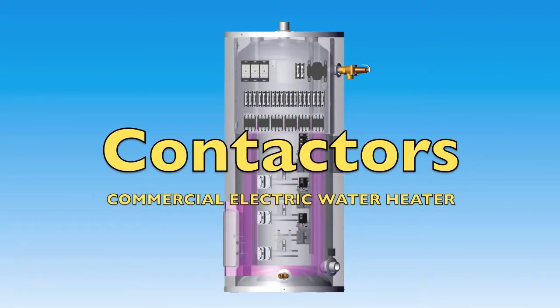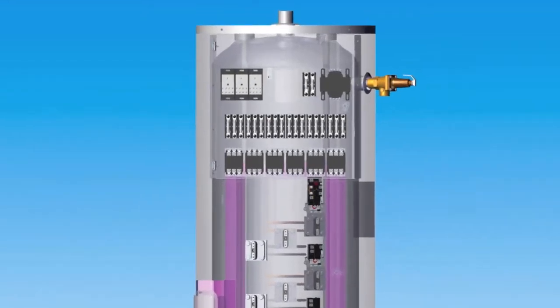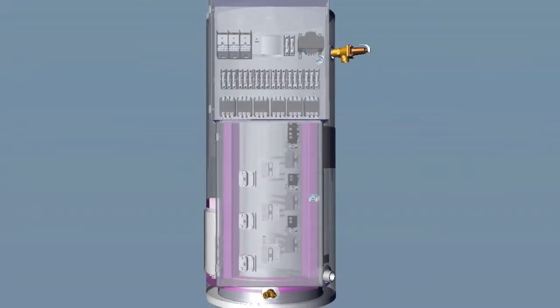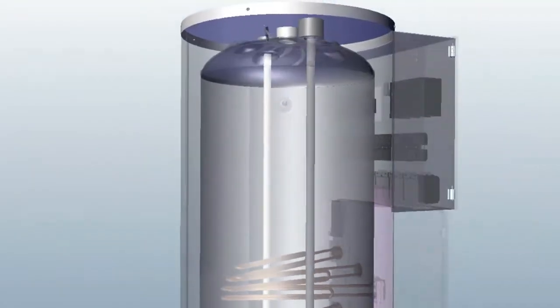Contactors. Each HTP commercial heater is equipped with one or more contactors, depending on the model, that supply power to the heating elements, providing that the ECO high limit is closed, the thermostat is below set point, and 120 volts AC is being supplied to contactors.